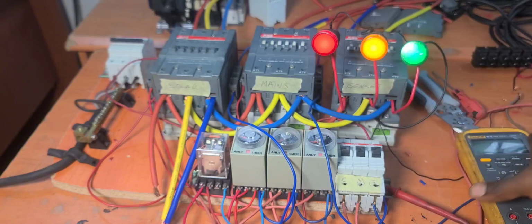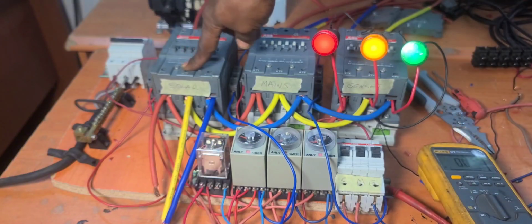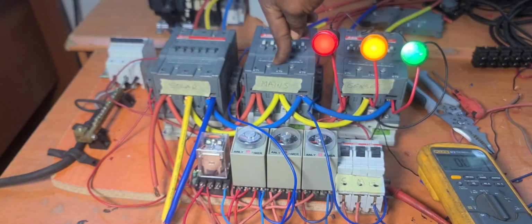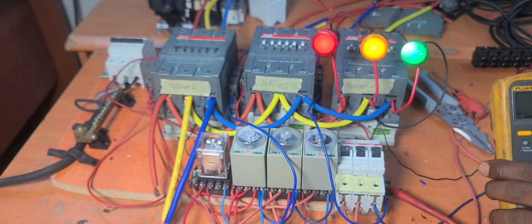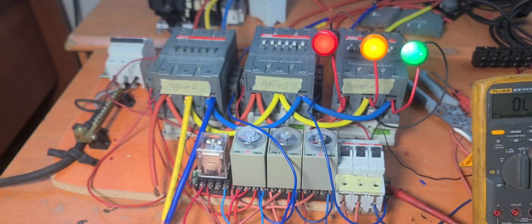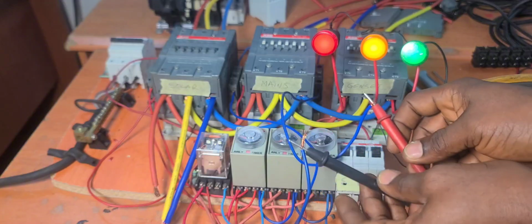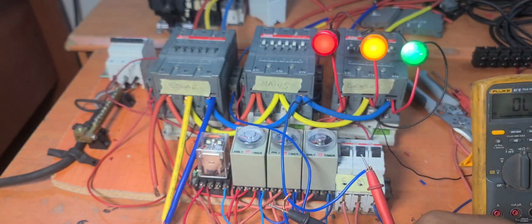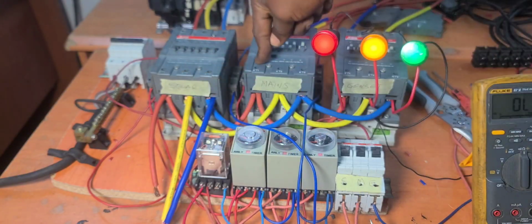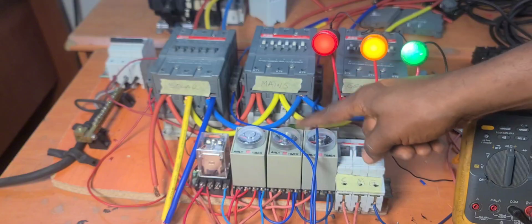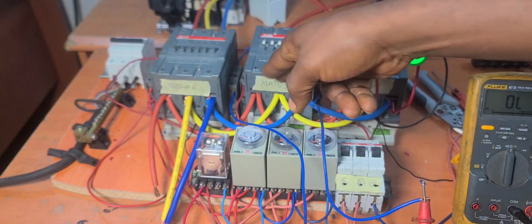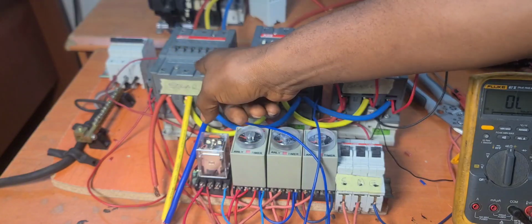So if this solar fails and this one is not active, we're going to have a continuous beep on this multimeter. And that continuous beep means that these two wires for this AMF, I'm talking of these two wires that are connected to the probes of this meter. What we're going to see when this one fails and this one fails is that there's going to be a beep, meaning that there is a continuity here, meaning this wire has short somewhere internally. So let us deactivate this one.